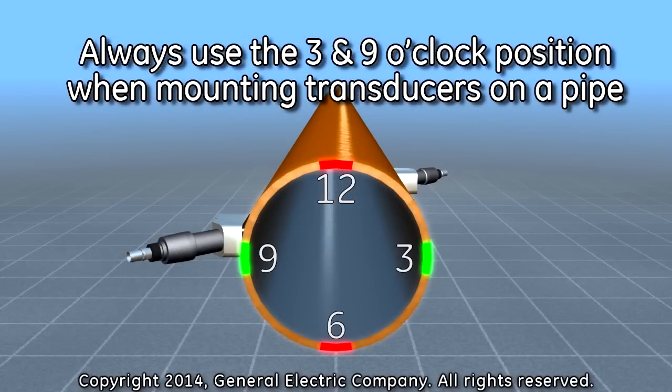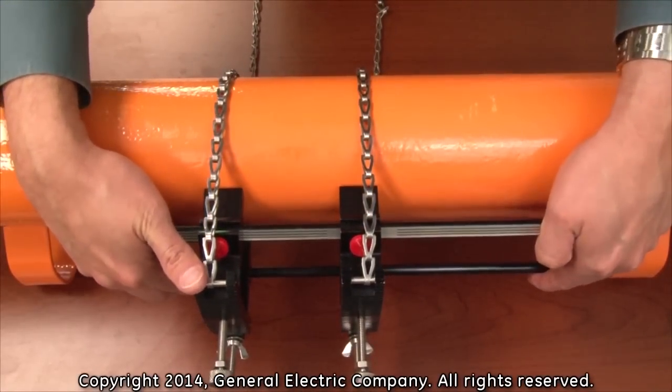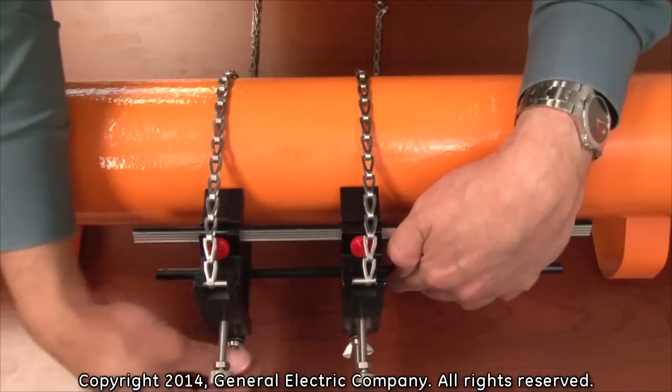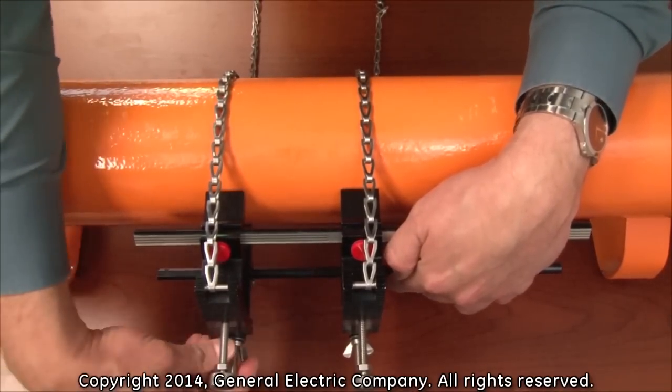Ensure that the clamping fixture is installed at the 3 o'clock or 9 o'clock position on the pipe, never at the 12 o'clock or 6 o'clock position. Tighten the wing nuts until the fixtures are secured firmly to the pipe.